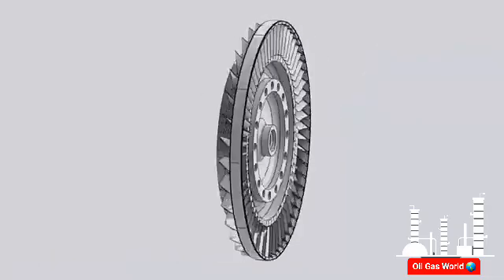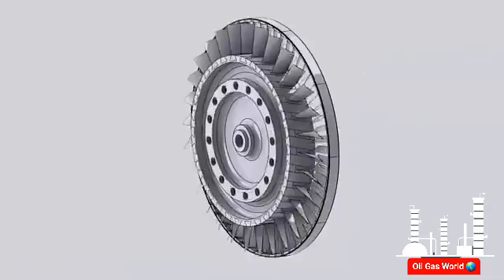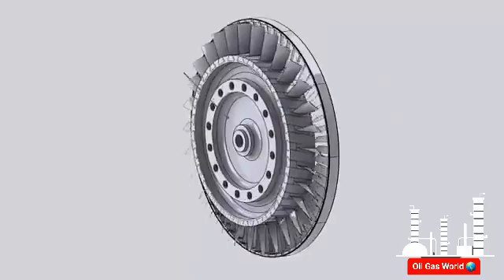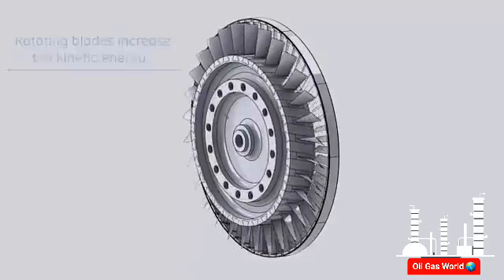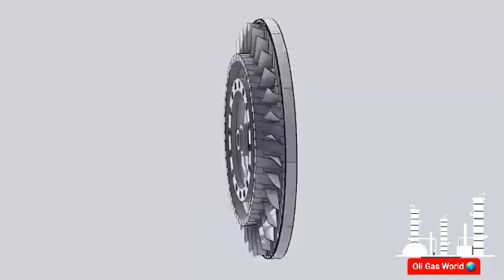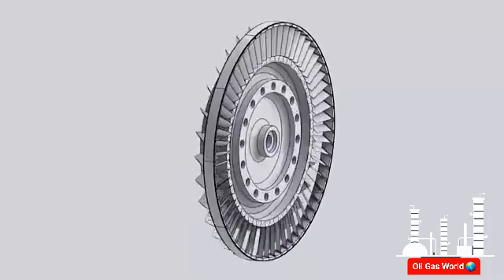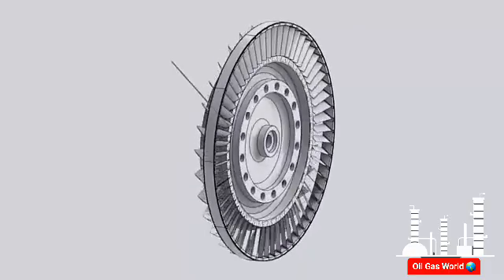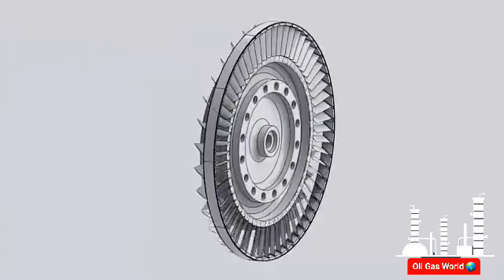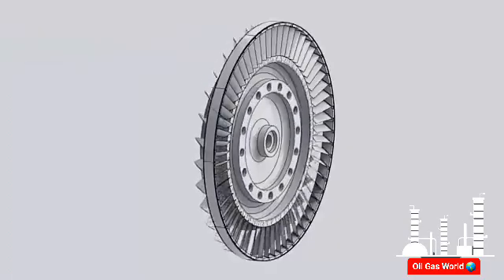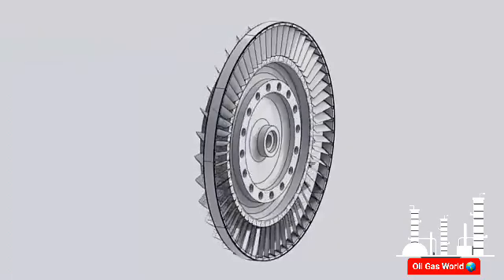Compression is achieved in each stage as the rotating blades increase the relative velocity of the air. The stator stationary blades then convert the gained kinetic energy into a pressure rise and guide air to enter the following stage at the proper angle.